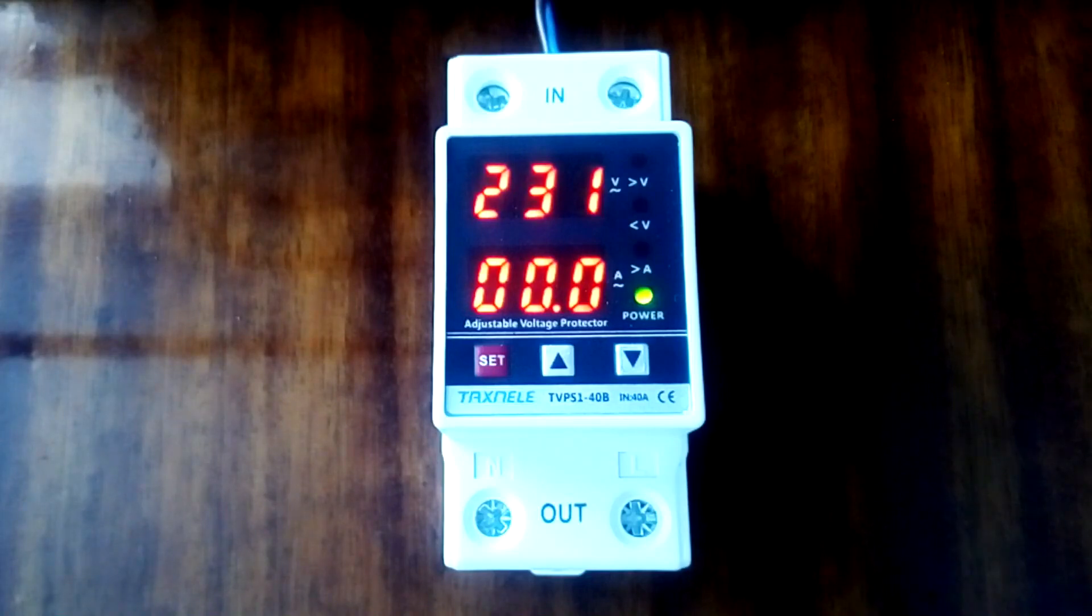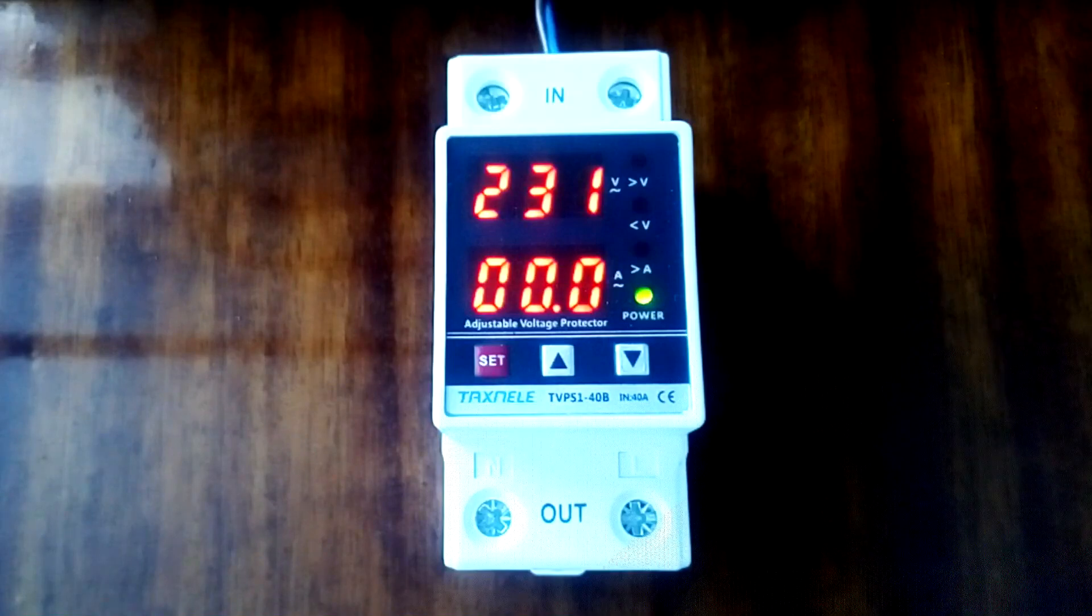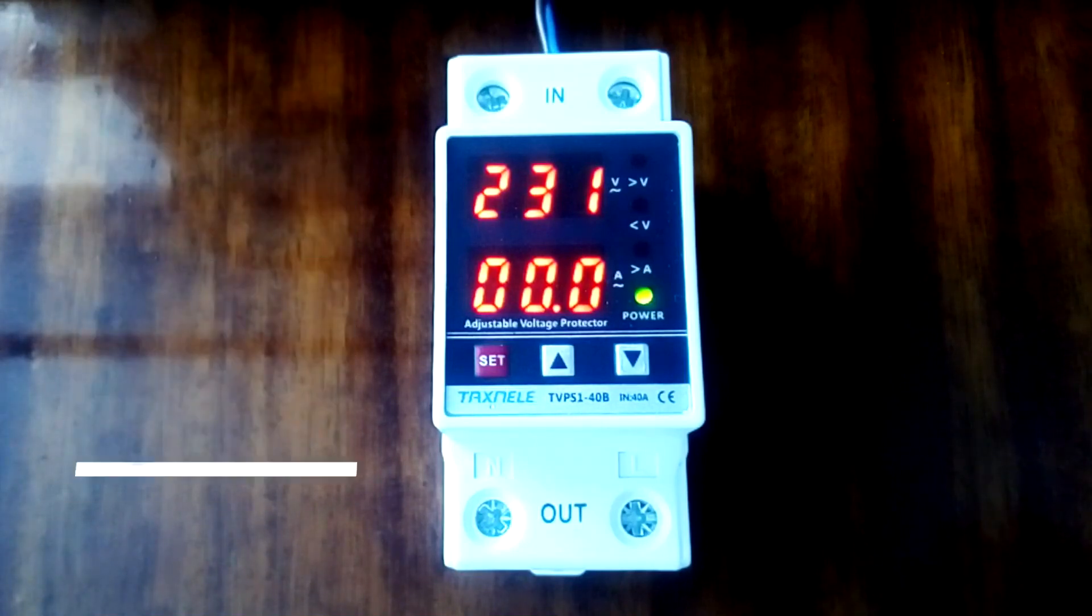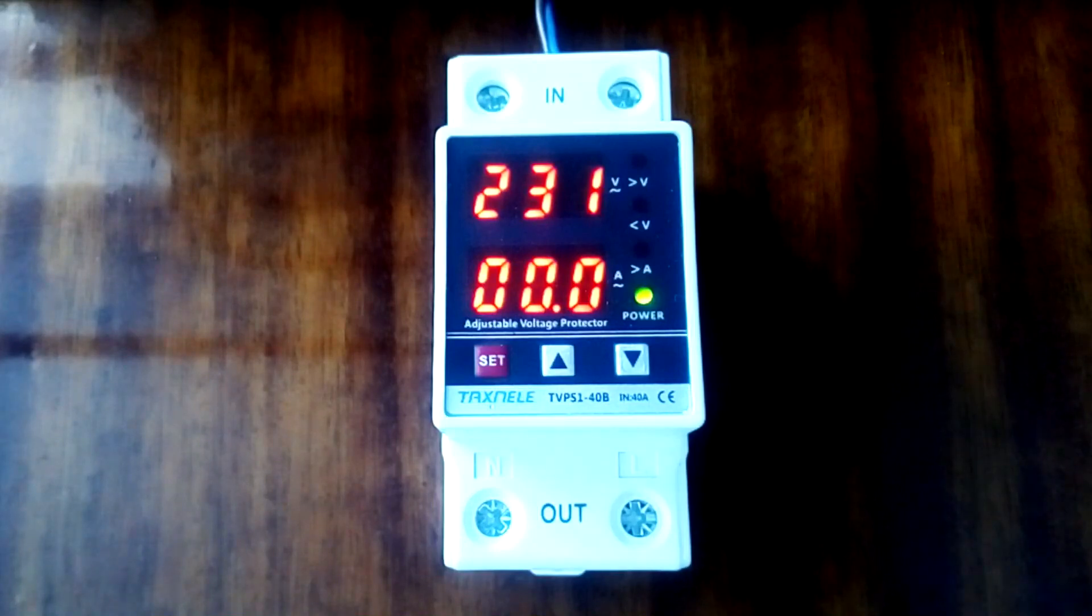Some appliances, such as gas boilers, require constant mains voltage. For this purpose, there are voltage stabilizers that can compensate for relatively slow voltage changes. Stabilizers should be used in conjunction with a voltage relay. They operate over a relatively narrow voltage range. When the voltage changes in this range, the stabilizer maintains the voltage around the nominal 230 volts. When the stabilization limits are exceeded, the voltage relay switches off the load. The relay is placed in front of the voltage stabilizer so that it protects the stabilizer from failure.